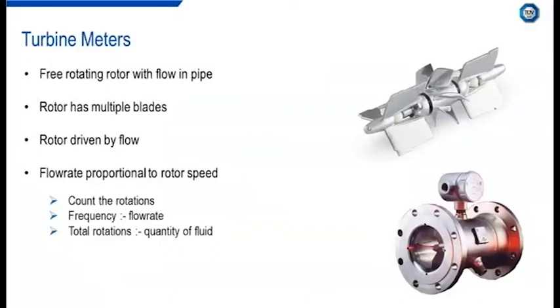Another type of metering technology, a very common type of single-phase metering technology, is the turbine flow meter. The turbine meter is used for high accuracy measurement of both liquids and gases. There are different designs depending on a liquid application versus a gas application for a turbine meter. A turbine flow meter consists of a multi-bladed rotor mounted on bearings, allowing it to rotate as it is driven by the flow. This gives a flow meter where the speed of rotation of the rotor is proportional to the volumetric flow rate of the fluid passing through it. Counting the number of rotations and the frequency of pulses per second gives the flow rate, and the total rotations gives the quantity of flow through the meter, or the total volume of fluid.